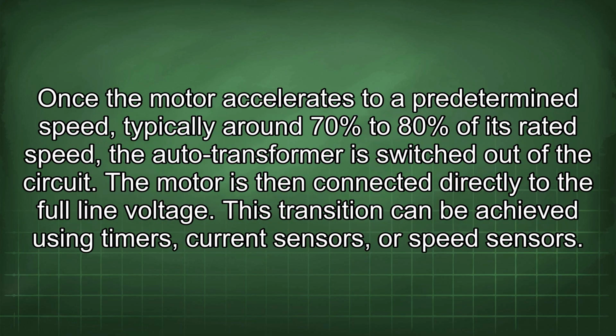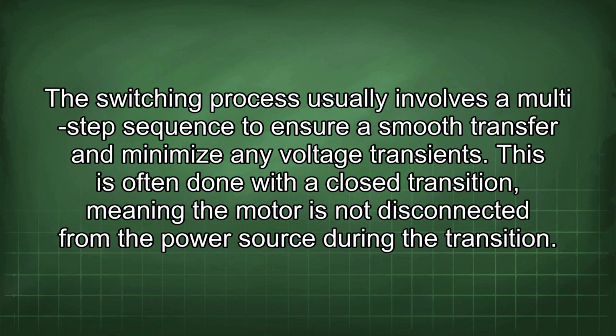Once the motor accelerates to a predetermined speed, typically around 70% to 80% of its rated speed, the auto-transformer is switched out of the circuit. The motor is then connected directly to the full line voltage. This transition can be achieved using timers, current sensors, or speed sensors. The switching process usually involves a multi-step sequence to ensure a smooth transfer and minimize any voltage transients.